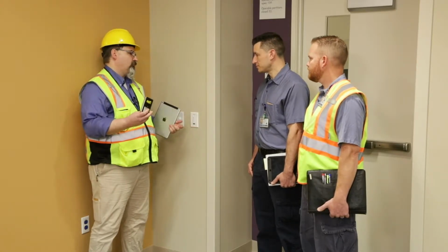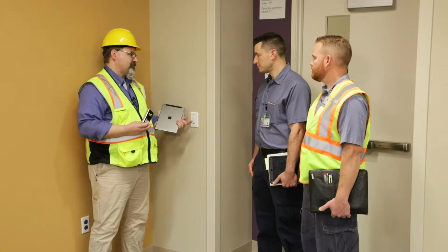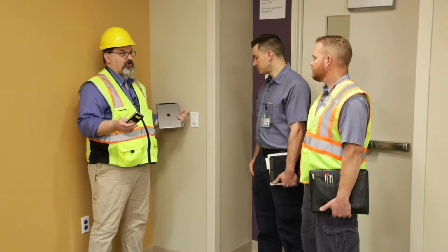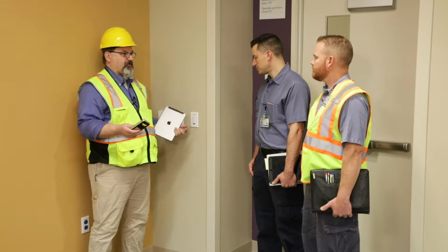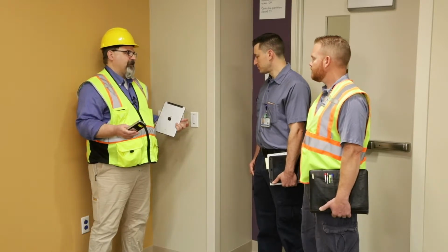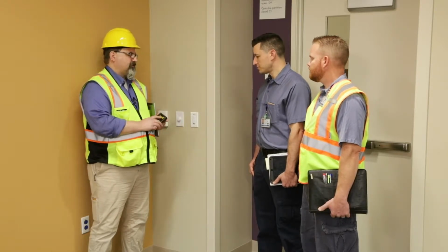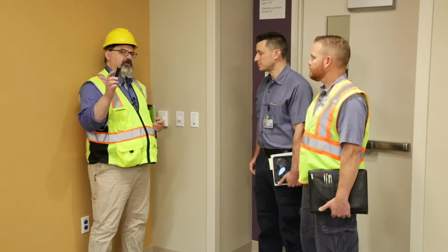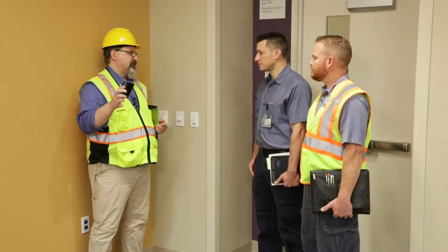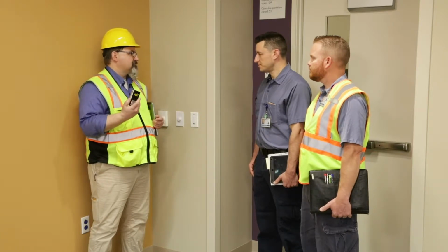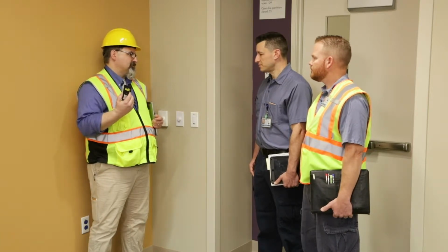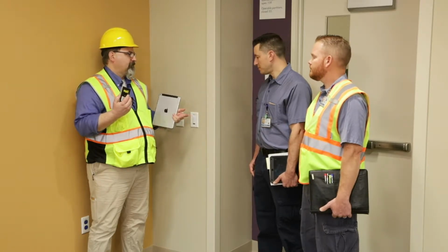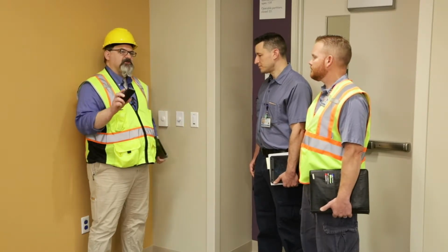We can control sensors and which loads they're associated with. We can make default levels for the lighting when you turn it on. It can come on to 100% or it can come on to 80%, right? And so that is what this enables. Also, throughout the building, there are some areas where there's daylight harvesting. And you can interface with the daylight harvesting and make changes to the way that works as well. And we'll go over that later in the lobby, okay? Because I definitely want you to see what it looks like in the lobby.